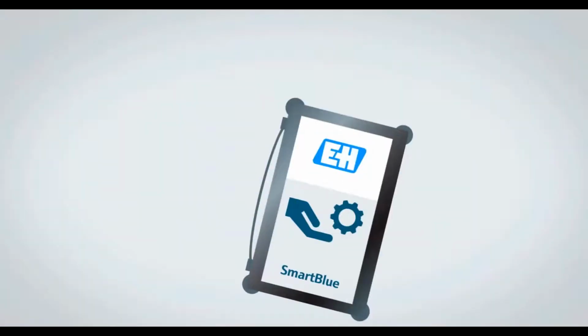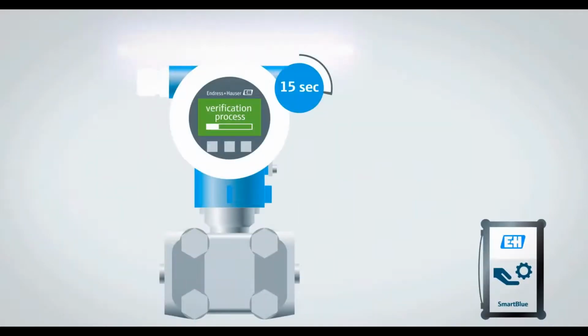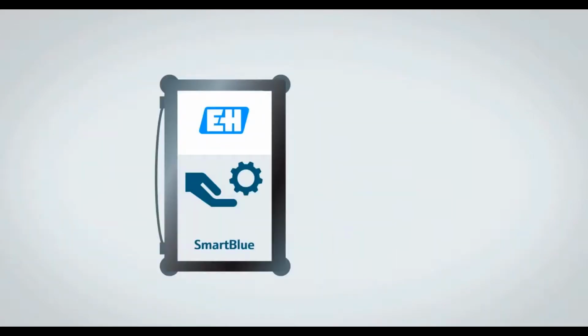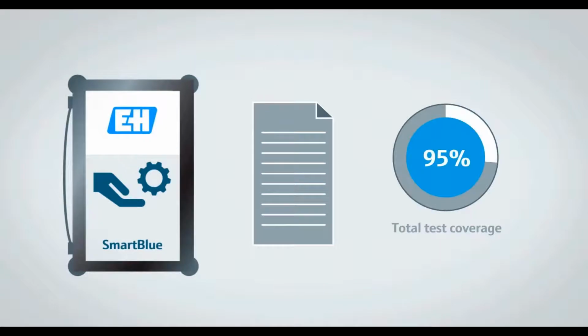All you need is a mobile device and the SmartBlue app. The big advantage of this app is the automatic updates. Searching for HART, EDD, or DTM libraries is a thing of the past. It updates automatically. All you have to do is type in your password, and it works quite well. Then after 15 seconds, you'll get an easy to read report with the results of the test. The total test coverage is more than 95%, and it also ensures testing of the most important functions of the device.